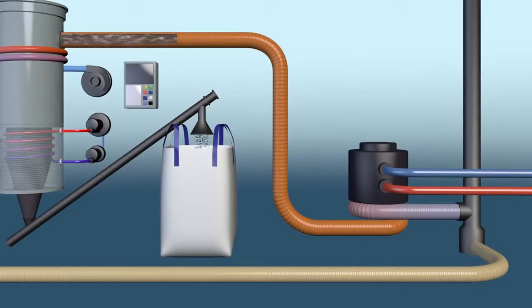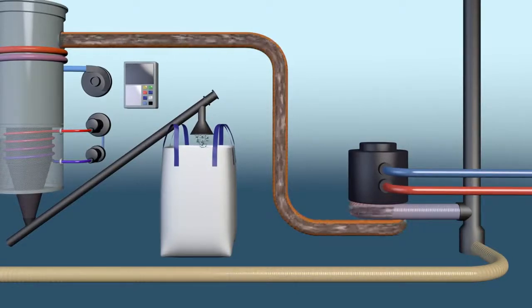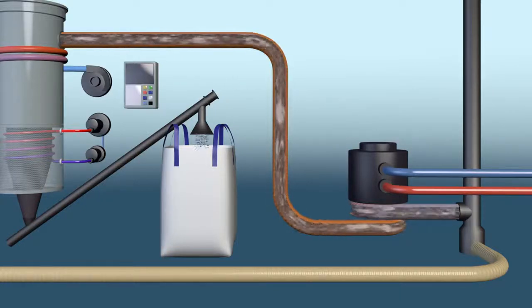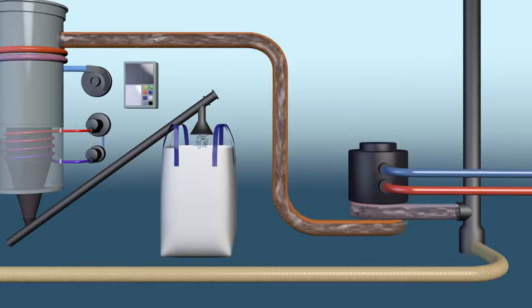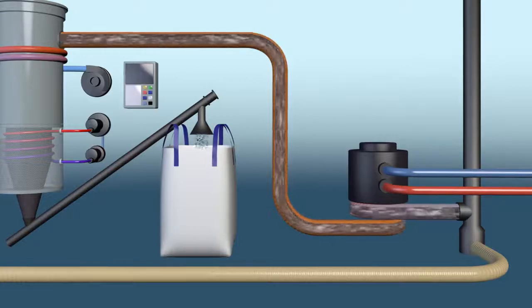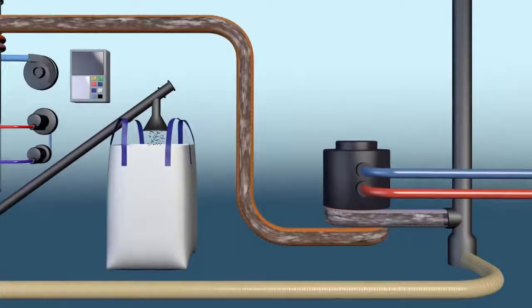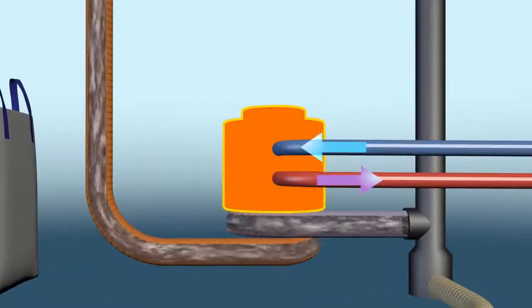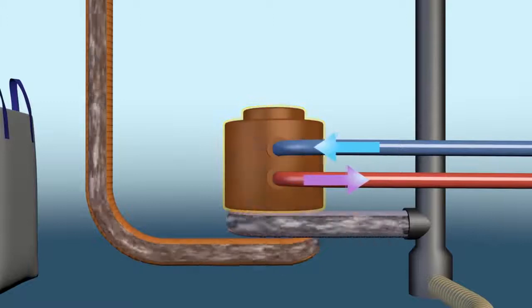Heat generation. The flammable gas has a relatively low calorific value, so the best way to make use of it is by conversion to hot water. Pyrolysis systems with productivity from 300 to 1,000 kilograms per hour can supply district heating networks with a maximum capacity from 1 to 3 megawatts, respectively.